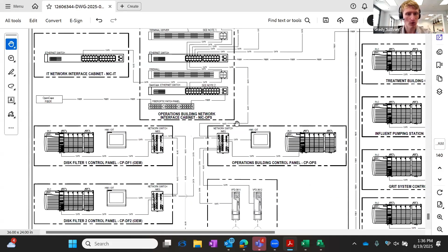So that's how we're going to be doing our remote connections. Using that internet connection, we'll have a firewall to prevent any unwanted access. We'll likely be using remote access software, something similar to LogMeIn. I'm not sure if anyone here has used it at other sites, but it's pretty simple remote access software to gain access to SCADA so operators can log in, say at 2 in the morning, and see if it's a nuisance alarm or something more serious that requires going into the plant to take a closer look.